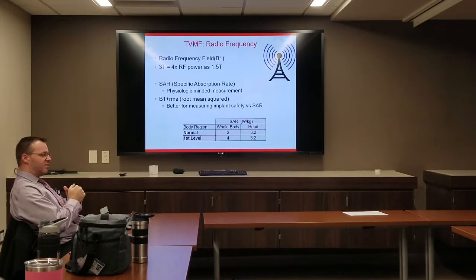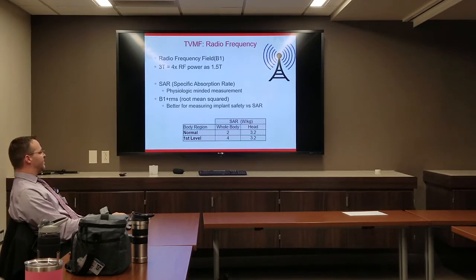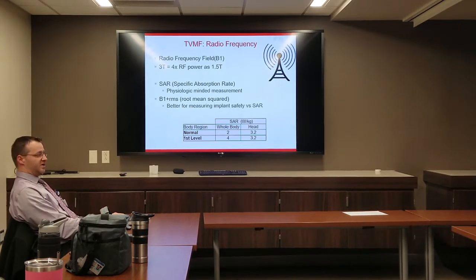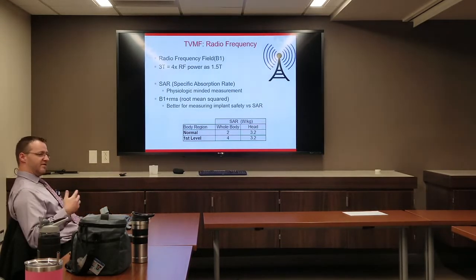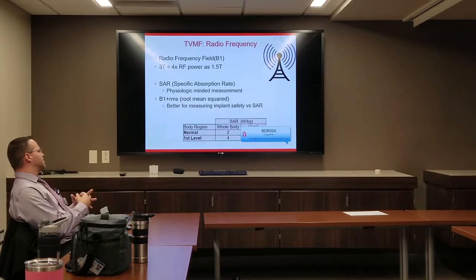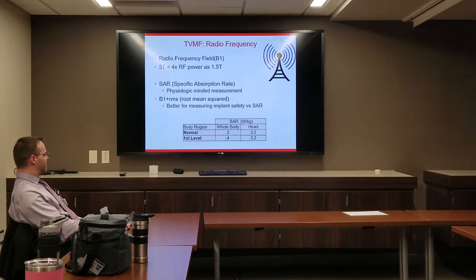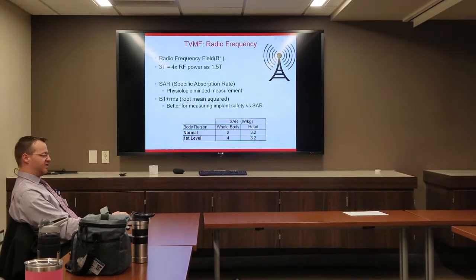Radio frequency fields are another form of time-variant magnetic field, also known as the B1 field. At 3 Tesla, the RF power is 4 times that at 1.5T — so maintaining SAR levels for an implant is much easier at 1.5T. For very large or obese patients where heating is a concern, 1.5T will also result in less heat. The two measurement methods are SAR (specific absorption rate), which is physiologically minded and accounts for patient height and weight, and B1+RMS (root mean squared), which is better for measuring implant safety. Operating modes include normal mode (2 W/kg whole body) and first level mode (4 W/kg whole body); head SAR is always 3.2 W/kg regardless of mode.